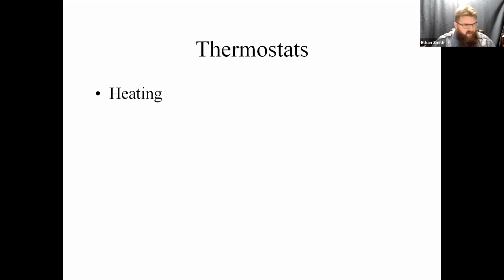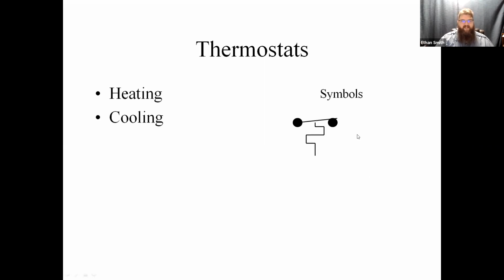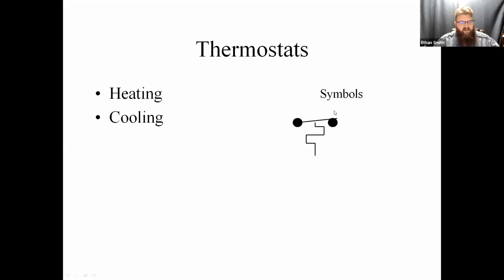Let's talk about thermostats. So what's a thermostat, guys? What is it really? It's a switch. It's a box full of thermally sensitive switches. Okay, heating, cooling, doesn't matter. It's a thermally activated switch, guys. Now in the age of digital, instead of thermally activated switches, we get relay activated switches. So like Keith says, switches are always going to be shown in their de-energized state on the wiring diagrams, unless otherwise noted. But modern thermostats, rather than having thermally activated switches in them, the digital thermostats, we're just using a temperature sensor to operate a relay, which again is just a switch. Okay, our industry lives and dies by switches.